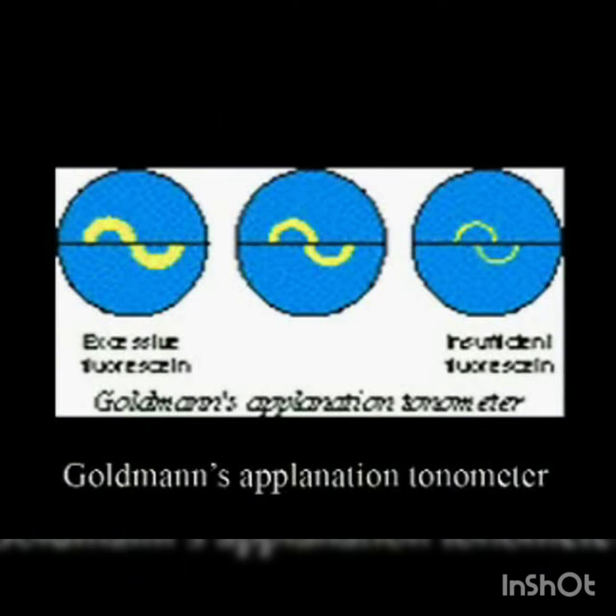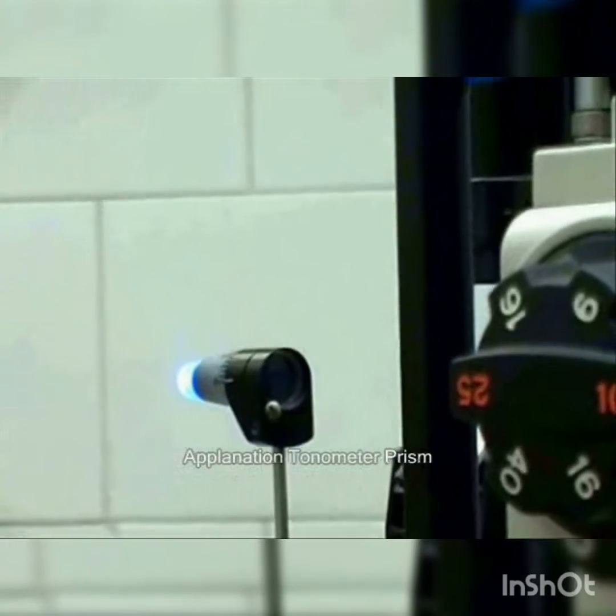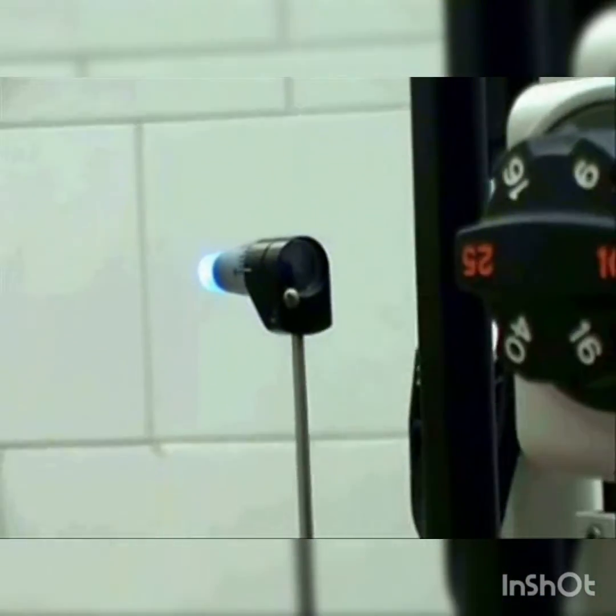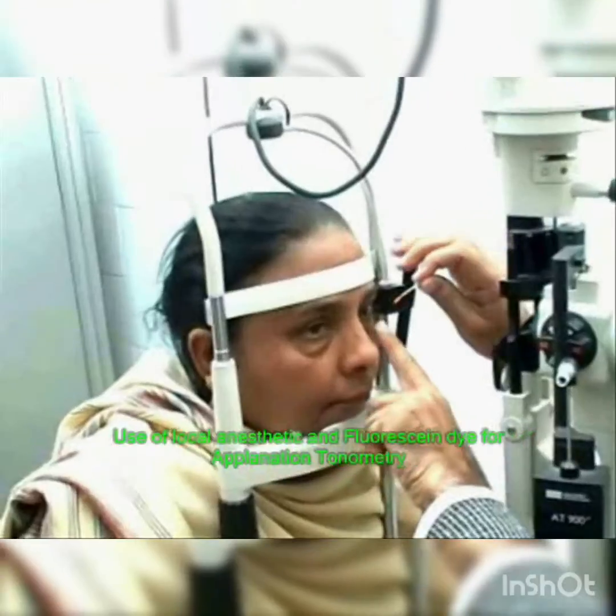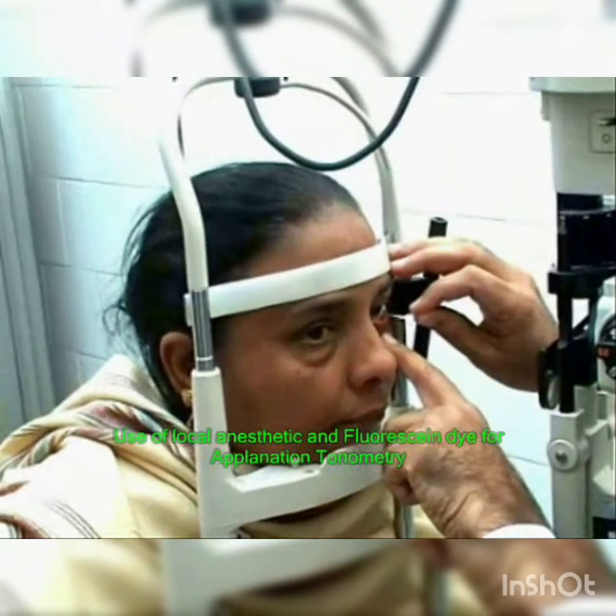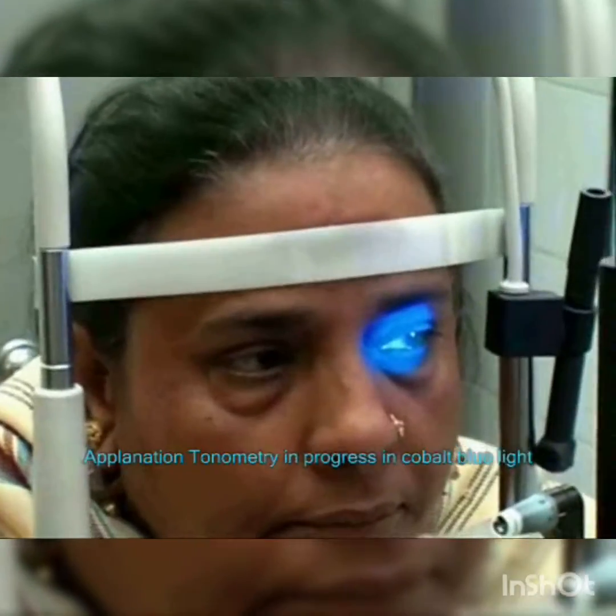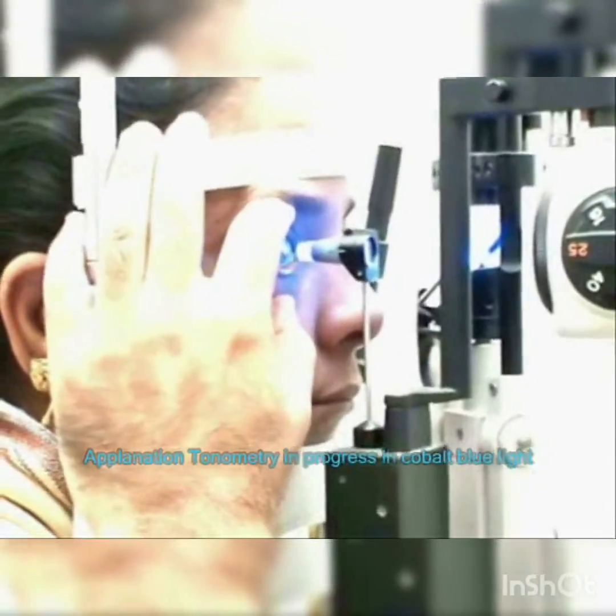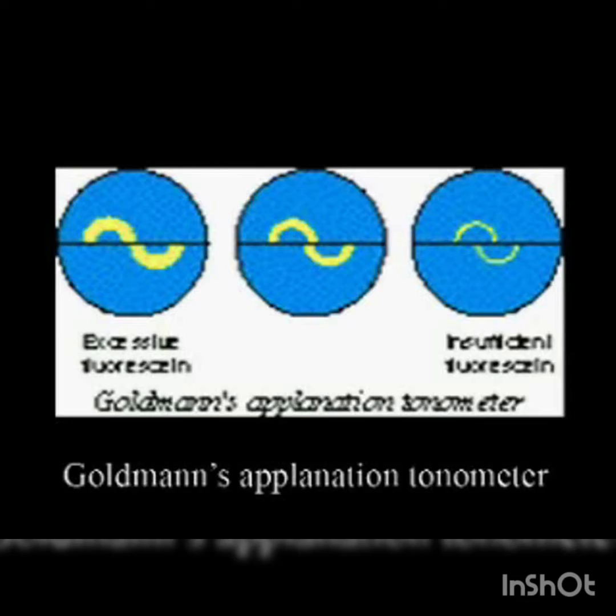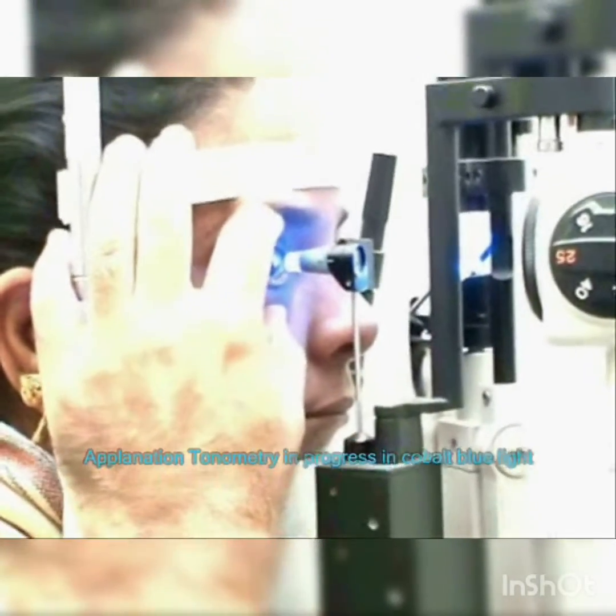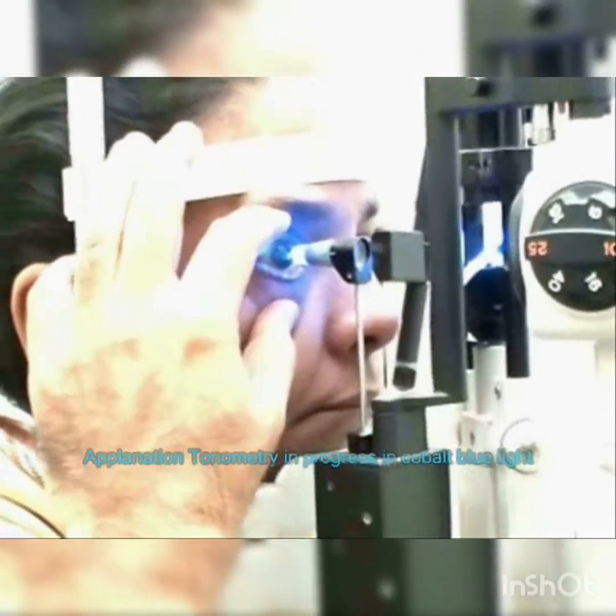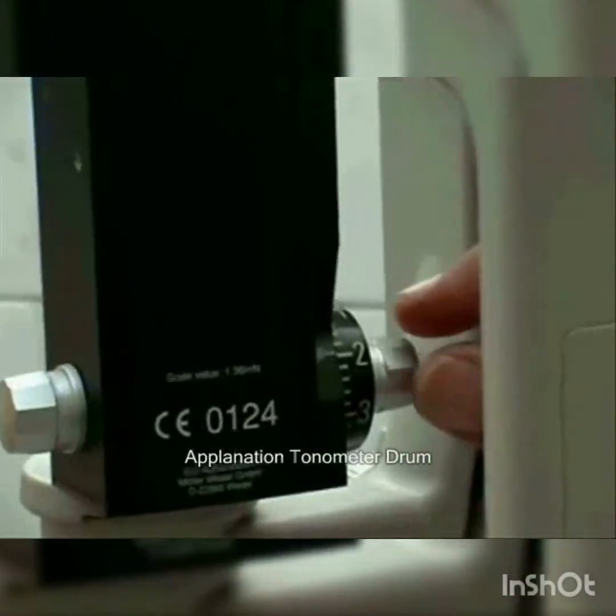The Goldmann applanation tonometer measures the force necessary to flatten a given area of the cornea. It is more accurate but requires greater experience. Fluorescein is used to stain the tears, and blue light is used to read the semicircle formed upon flattening of the cornea by the applanation prism. Reading is read at a drum towards the base of the tonometer.